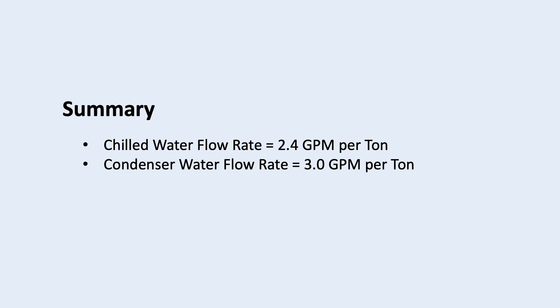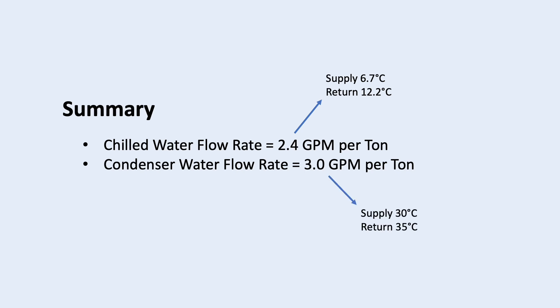However, remember that 2.4 is based on 6.7 and 12.2 degrees Celsius of chilled water supply and return temperature. And 3.0 for the condenser water is based on 30 degrees Celsius and 35 degrees Celsius condenser supply and return temperature. If any of these design temperatures change, the rule of thumb value will also change.